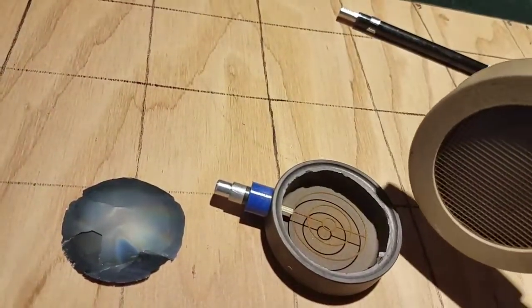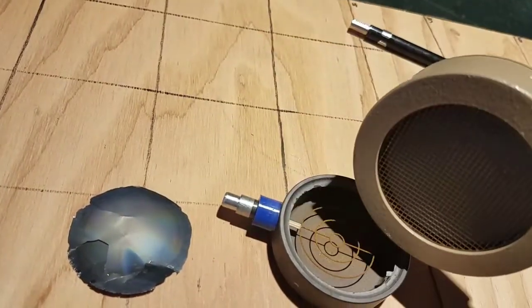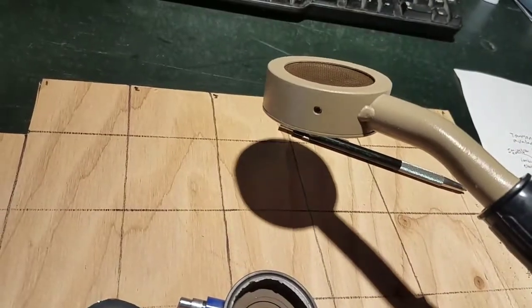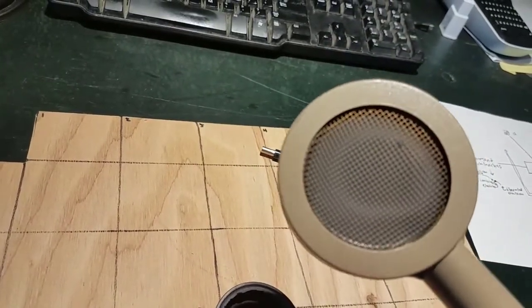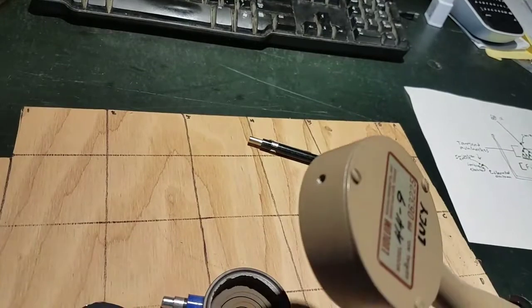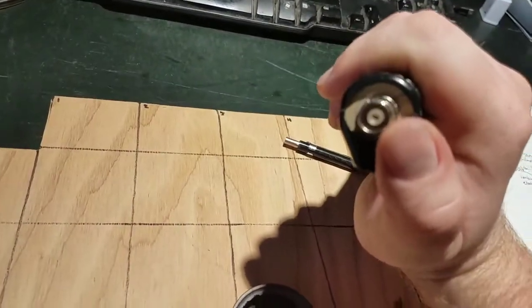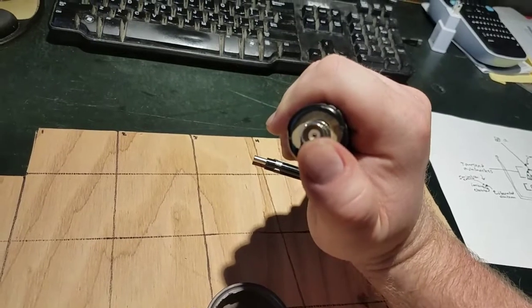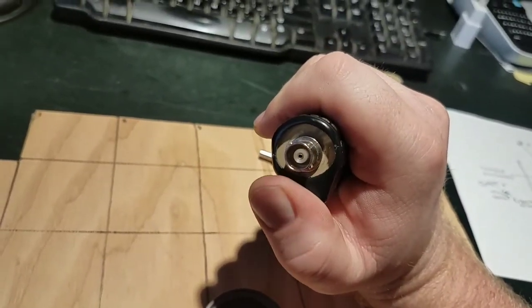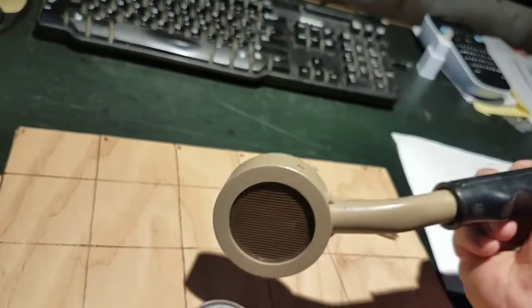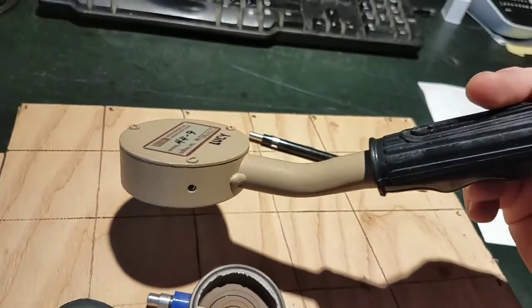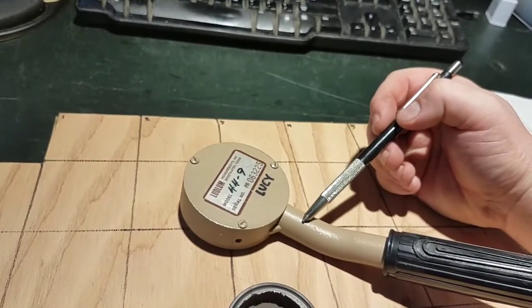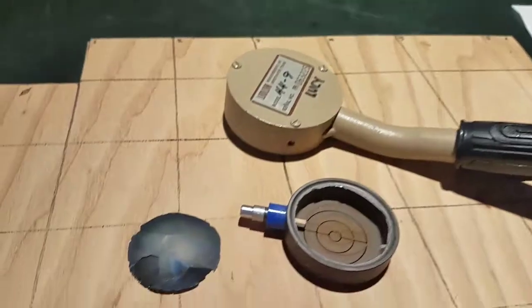Basically I took this damaged probe out of this probe here. You can see here the three set screws that we use to hold and center the probe, and a little protective screen on top of it. It's actually really simple inside. The outside of this connector is the cathode and the anode wire. There's a little gold connector in there which is the anode, and that allows voltage to pass through some anode resistors which are inside the neck of the detector. They sit right about here and directly connect to the little shoe connector that you clip on.